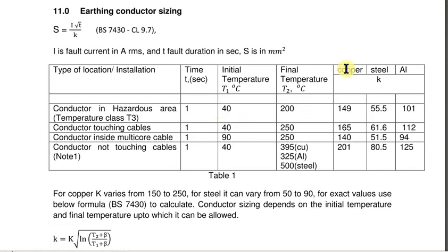Copper, steel is given. Aluminum I don't use normally because of corrosion problems. For example, if it is steel for a 40 kA fault current, that is 40,000 divided by 55 gives you somewhere around 750 mm square. So that is how you determine the size. After you determine the size, you have to add some margin for corrosion. I will tell you about that later. Thank you.